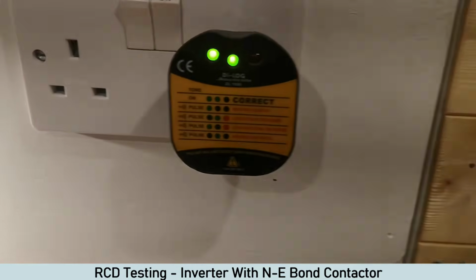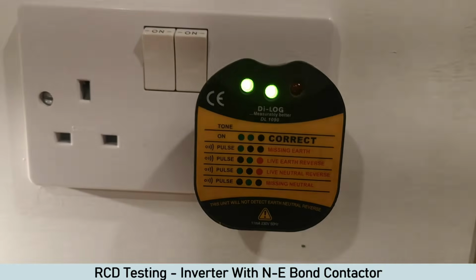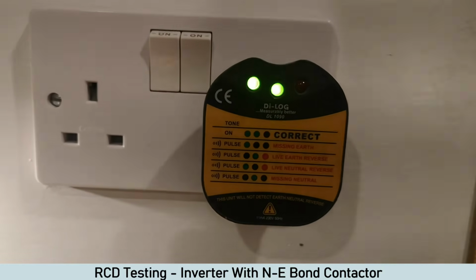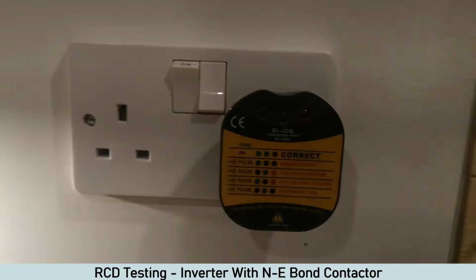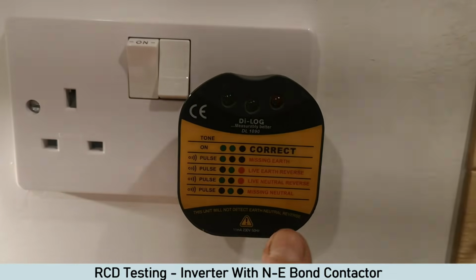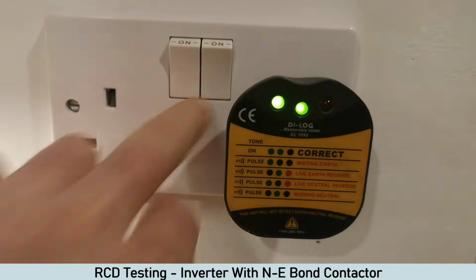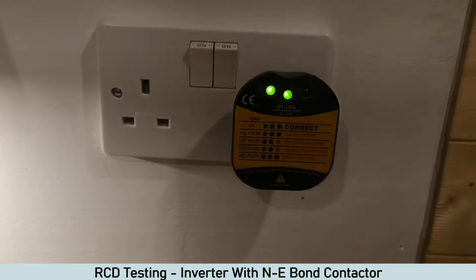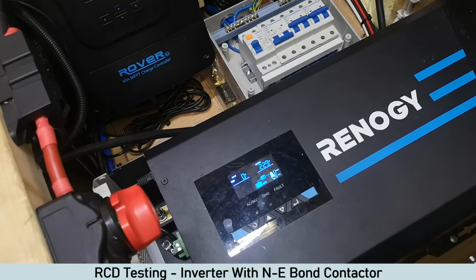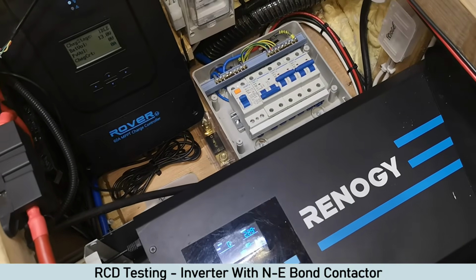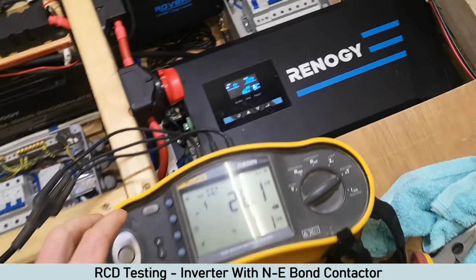Go up to here, and there we go. So as before with the inverter, sorry, switch that off again. As before with the inverter, it came up as a live neutral reverse, whereas now it's correct, it's good. So to prove even further that the RCD works, I've got my RCD tester here.